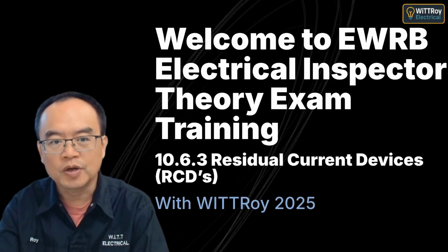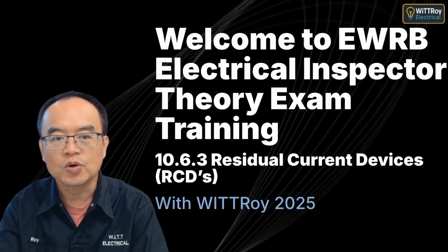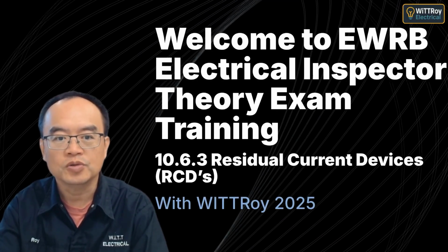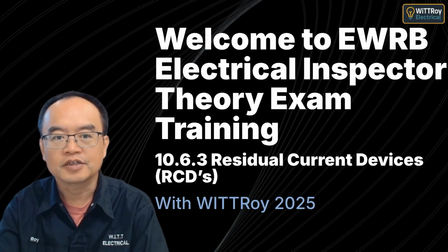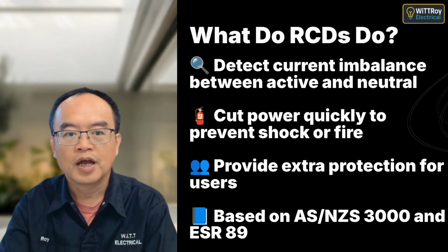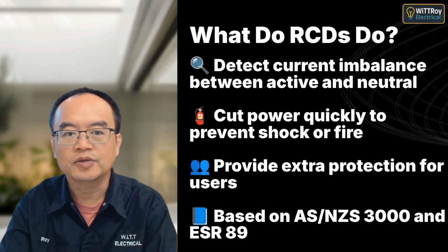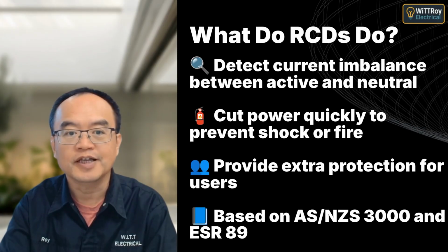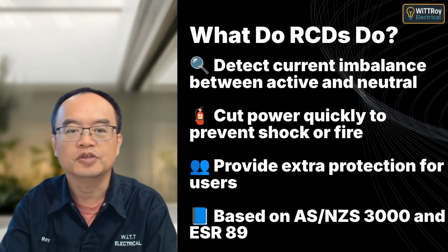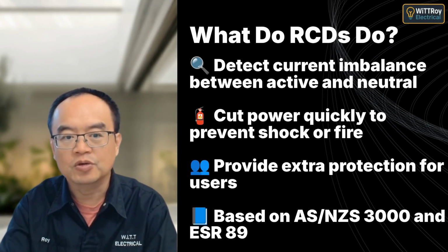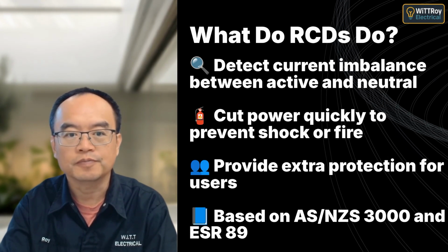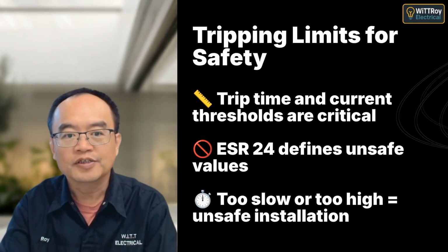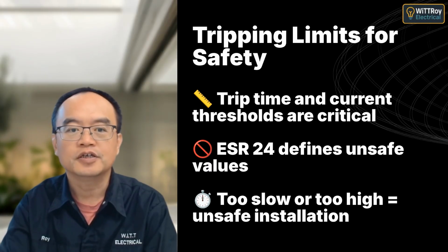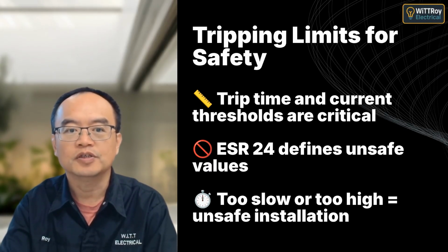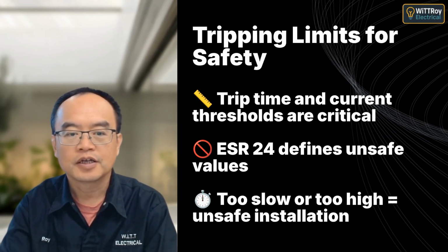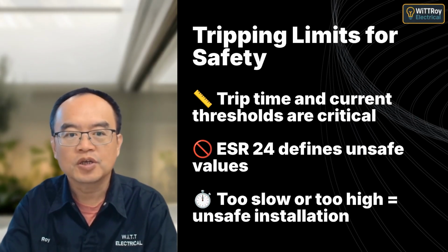Hi everyone, I'm Whitroy. In this short lesson, we'll explore RCDs, how they work, where they're used, and what standards guide their selection and installation. RCDs work by monitoring current flow and disconnecting the supply when leakage is detected. This helps protect users from electric shock and can prevent fires caused by current escaping to earth. According to ESR 24, an RCD that doesn't trip within the required current or time is deemed unsafe. This is why testing and compliance are essential in all installations.